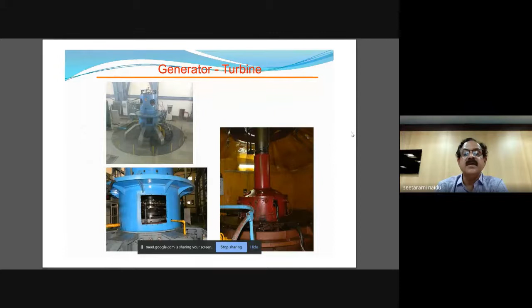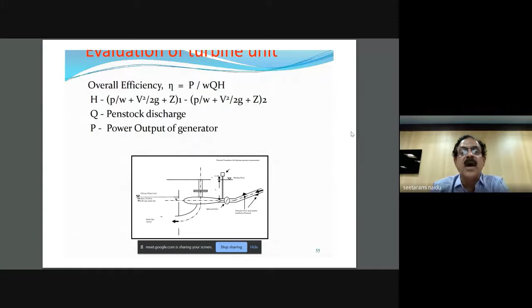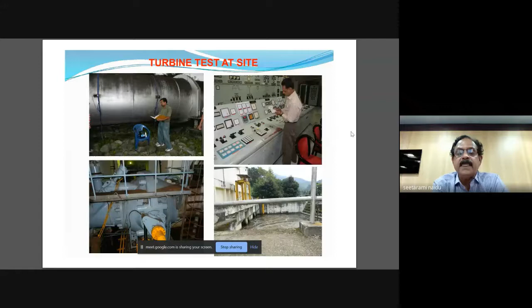Photographs. Say this, you know how to evaluate efficiency. Efficiency is power output divided by gamma, specific weight, times discharge in meter cube per second, times head in meter. This gives efficiency. P is in megawatt, the generator output, so this is the overall efficiency of the plant. But usually, to evaluate the turbine, we have to assume some generator efficiency, divide the megawatt by the generator efficiency, and come to the turbine output. Okay, I hope you are clear. Are you with me? This is the arrangement. The main parameters measured are discharge, power, the input pressure, then tail race water level variations.